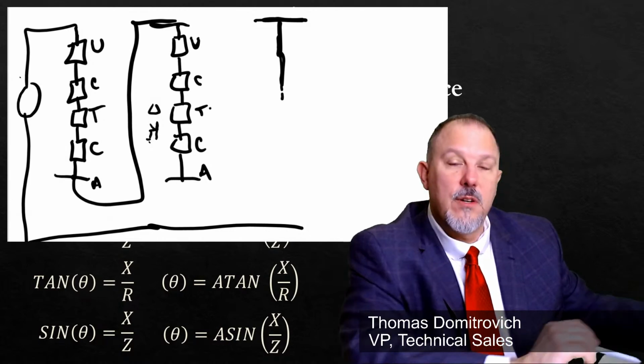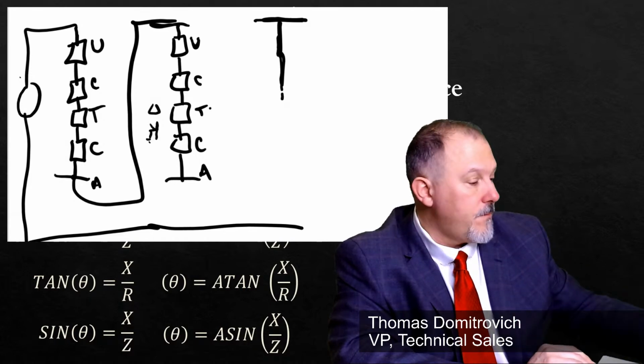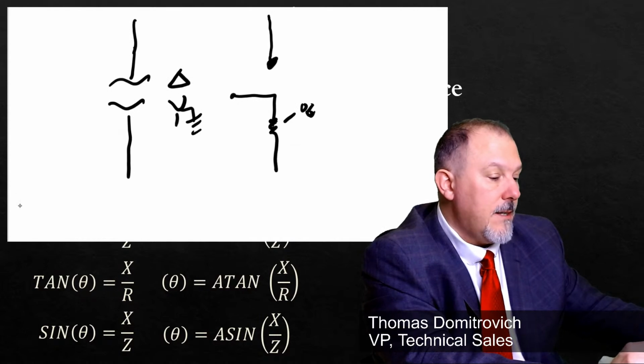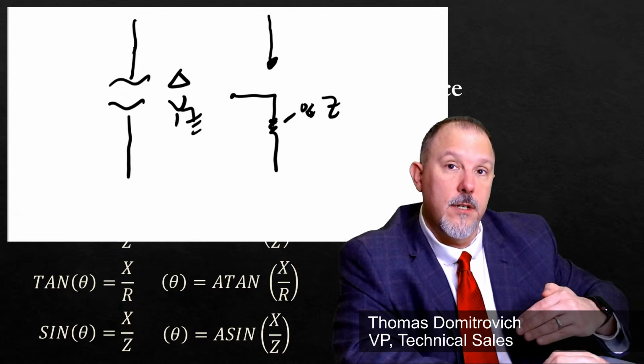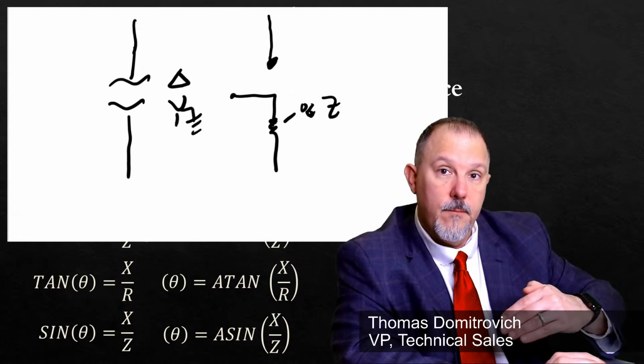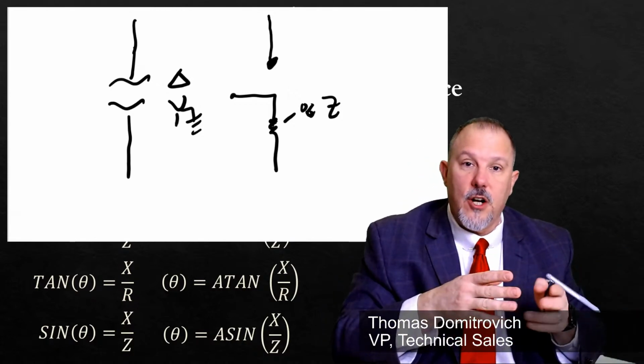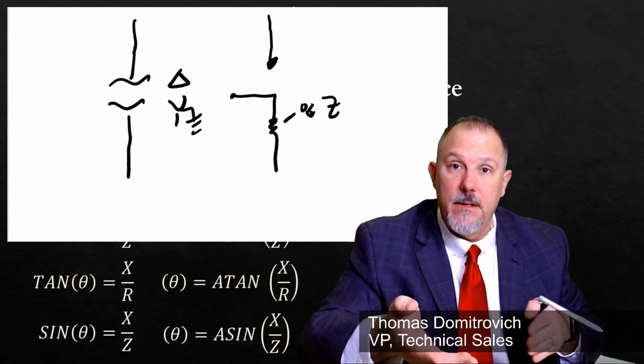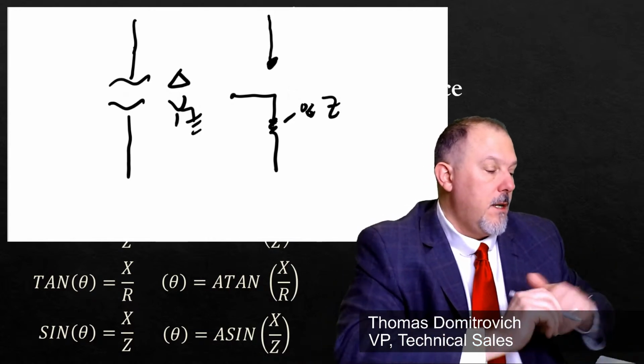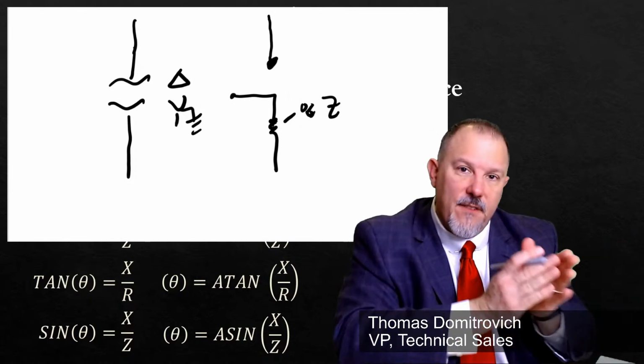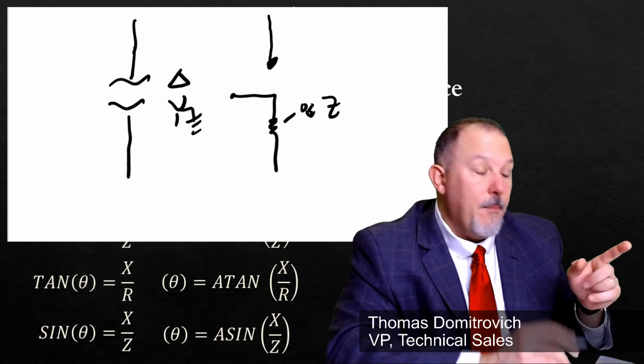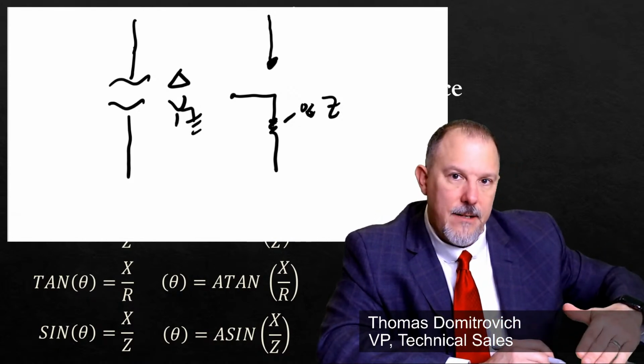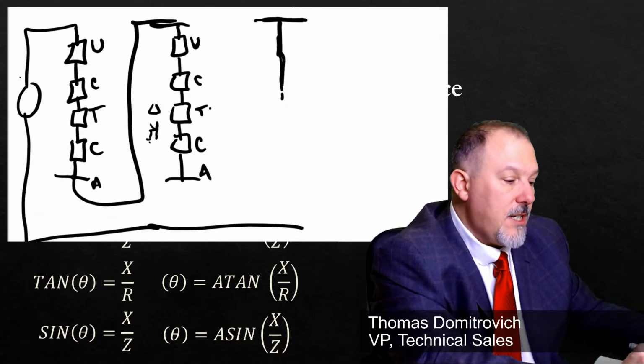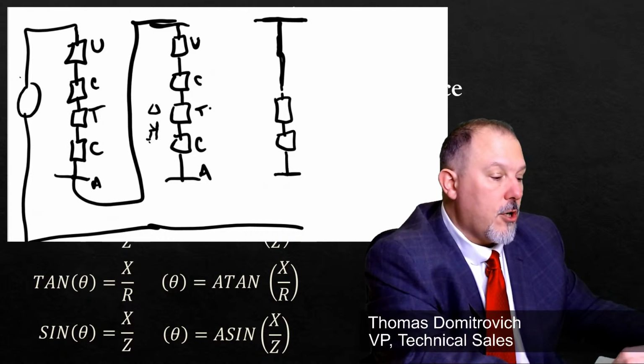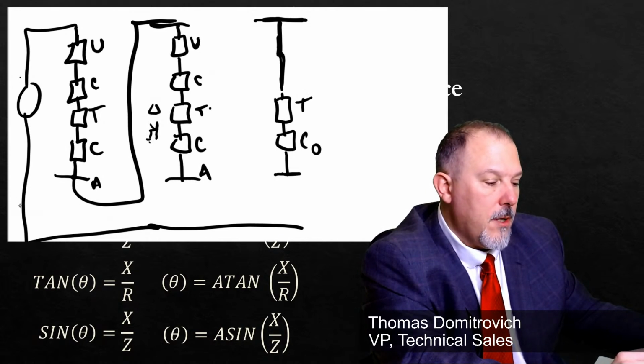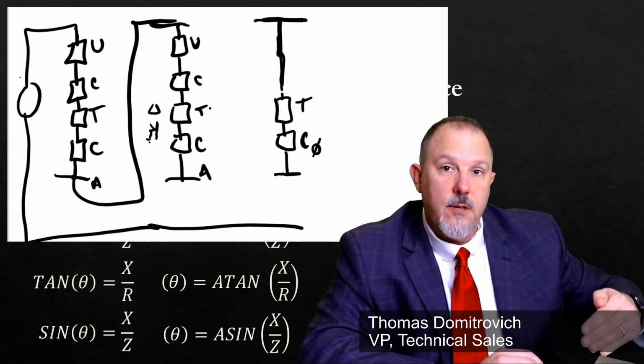Now, the transformer has a delta primary, but it has a Y grounded secondary. If I look at this, this is my %Z for that transformer. It is a part of my zero sequence circuit because it's a Y grounded. All of my zero sequence currents will go to ground, right? And they will add up when they go to ground. Make sense? Hopefully. Because they're in phase with each other, they won't go through that delta. That's isolated. I don't include the impedances upstream. So my zero sequence circuit will include the transformer and the conductor, and I'm going to put a little 0 down the bottom. The zero sequence impedance of the conductor.